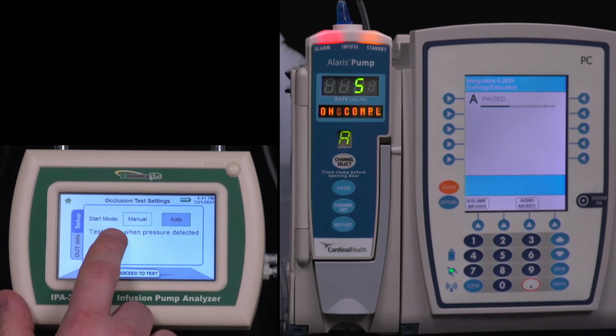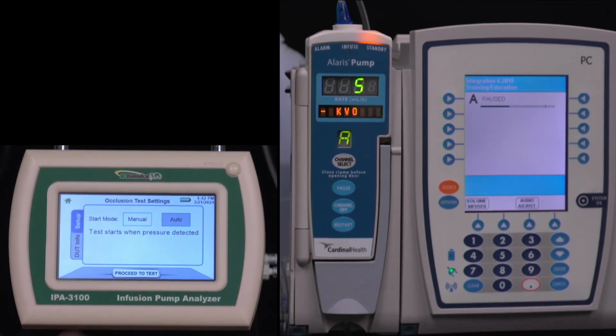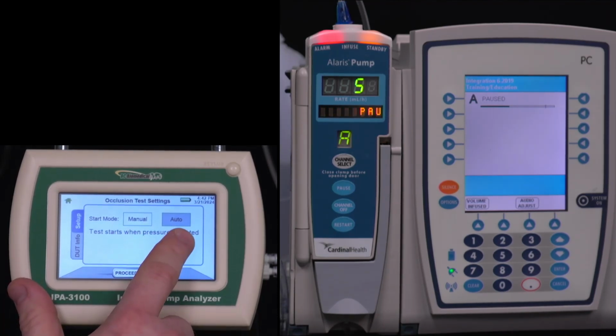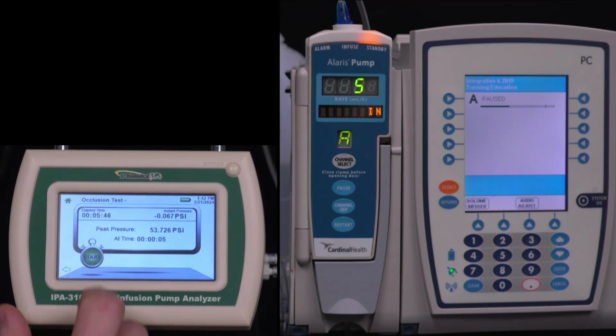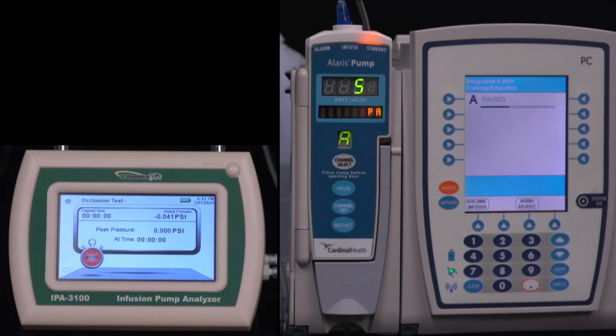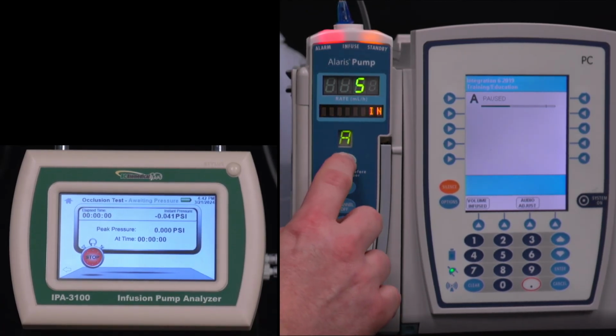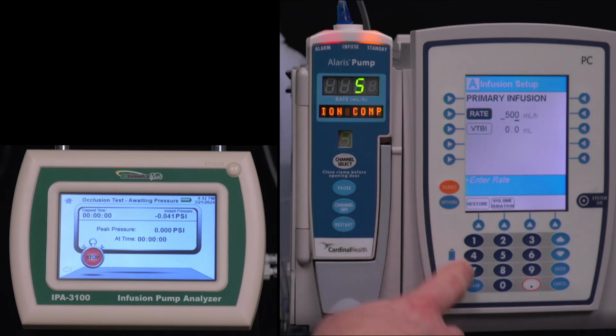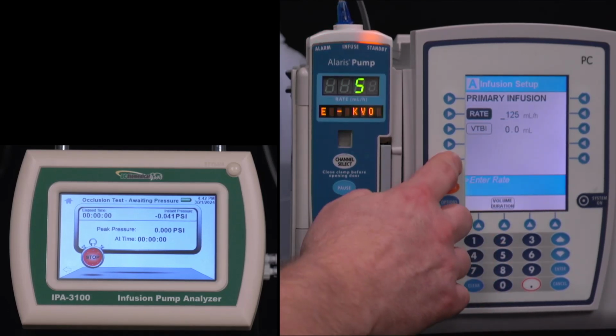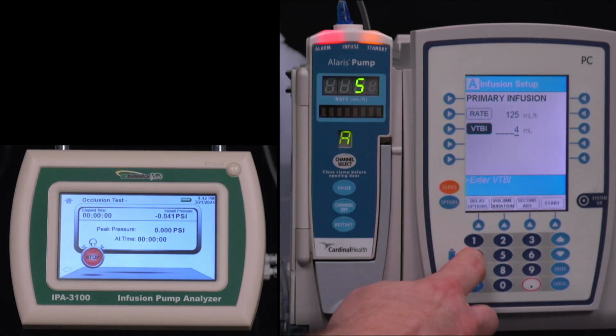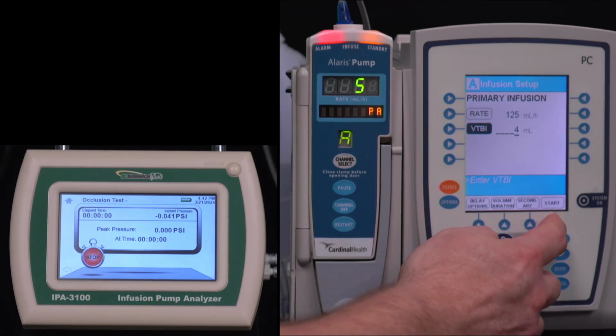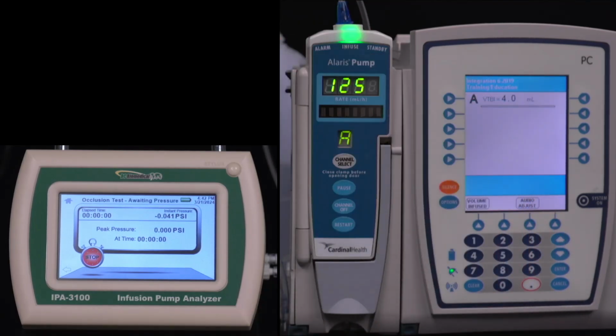Okay, so the other test we can do is occlusion. Similar to the other test, if we start manually, it'll start the timer as soon as we start the test. If we do auto, then it's going to wait to start the test until it sees pressure. So it's idle, awaiting pressure at the top. All I have to do is set the pump. And for our occlusion testing, it's 125 milliliters per hour, and they say dispense 4 milliliters. So we'll go ahead and do that.